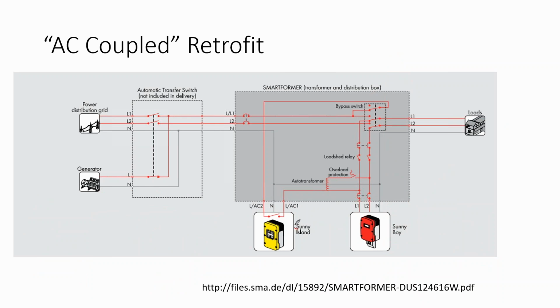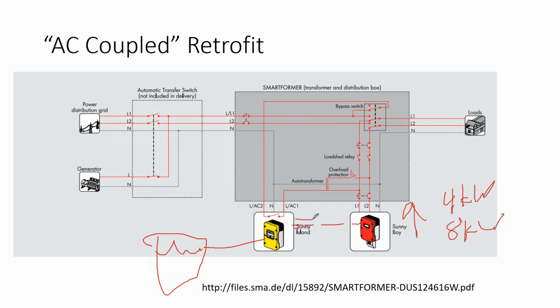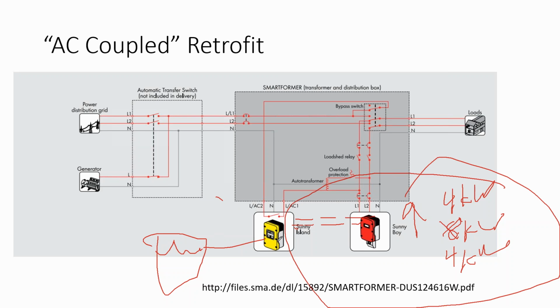In another circumstance, the batteries are full and your solar array is on and your home is using 4 kilowatts of load and your solar array is at 8 kilowatts and your battery inverter tells your solar inverter, hey, just dial it back a little, dial it back to 4 kilowatts. And so that way you're using your solar array and you're not using your batteries during the day when your batteries are full.